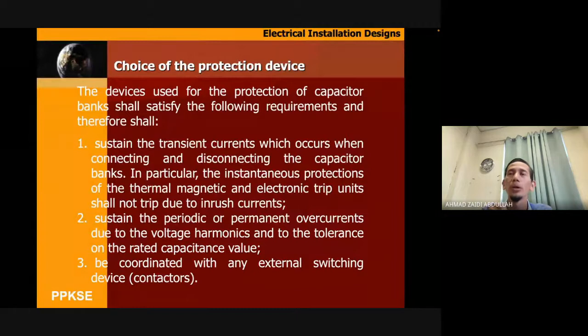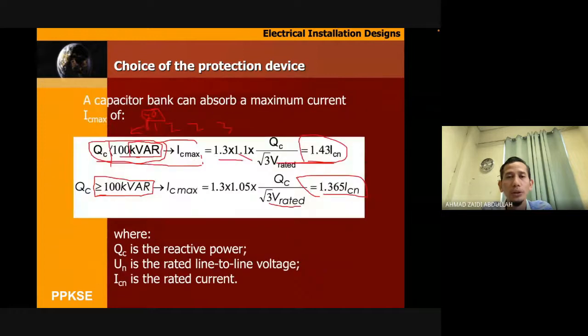Because when we're dealing with installation design, we have a lot of breakers, and when we're dealing with breakers, confirm there will be switching on and off. When we have switching on and off, confirm there will be inrush current. So that's why we need to install protection devices, including the breaker and also the contactor, in our power factor correction system.